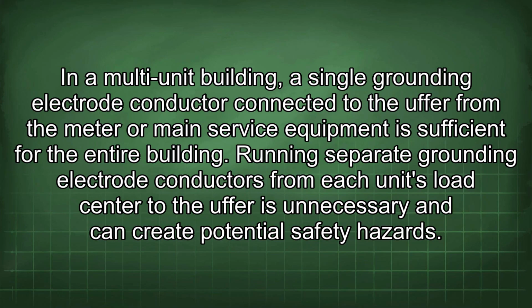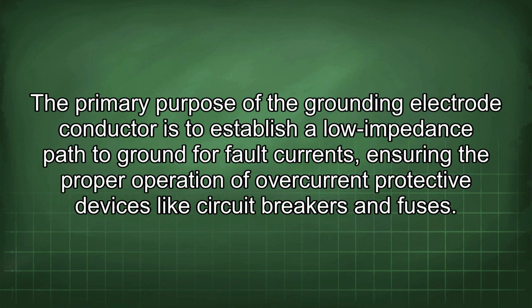In a multi-unit building, a single grounding electrode conductor connected to the Ufer from the meter or main service equipment is sufficient for the entire building. Running separate grounding electrode conductors from each unit's load center to the Ufer is unnecessary and can create potential safety hazards. The primary purpose of the grounding electrode conductor is to establish a low impedance path to ground for fault currents, ensuring the proper operation of overcurrent protective devices like circuit breakers and fuses.